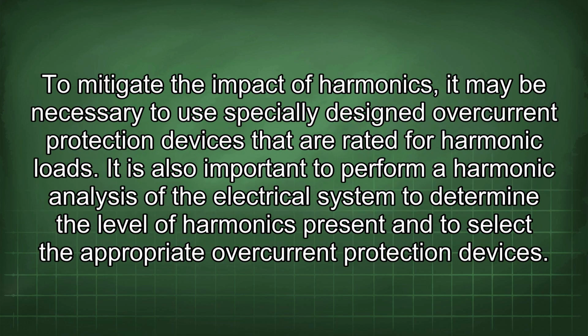To mitigate the impact of harmonics, it may be necessary to use specially designed overcurrent protection devices that are rated for harmonic loads. It is also important to perform a harmonic analysis of the electrical system to determine the level of harmonics present and to select the appropriate overcurrent protection devices.